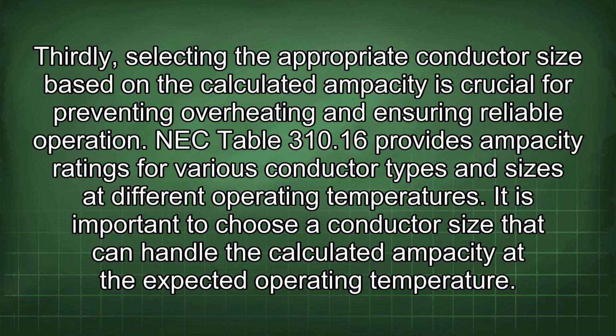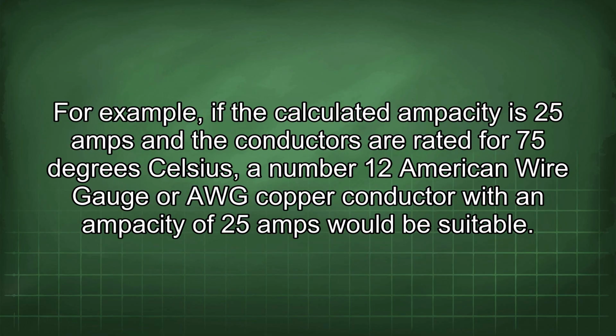Thirdly, selecting the appropriate conductor size based on the calculated ampacity is crucial for preventing overheating and ensuring reliable operation. NEC Table 310.16 provides ampacity ratings for various conductor types and sizes at different operating temperatures. It is important to choose a conductor size that can handle the calculated ampacity at the expected operating temperature. For example, if the calculated ampacity is 25 amps and the conductors are rated for 75 degrees Celsius, a number 12 American wire gauge, or AWG, copper conductor with an ampacity of 25 amps would be suitable.